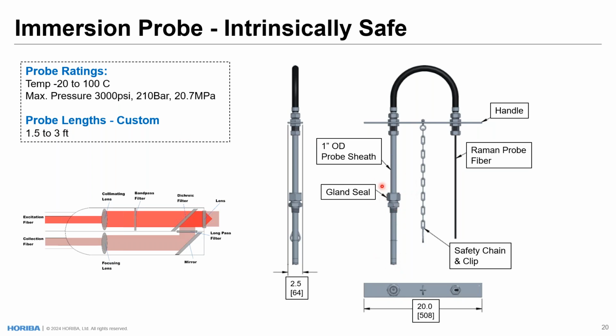The gland seal that we outfit in the immersion probe ensures that no product or sample will ever leach into your immersion probe, which could, of course, bring the potential of messing up the optics inside the actual immersion probe and getting stuff stuck where stuff should not be stuck. So the gland seal really prevents that from happening, which allows your process stream to be safe, as well as the hardware for the analyzer to be safe as well.